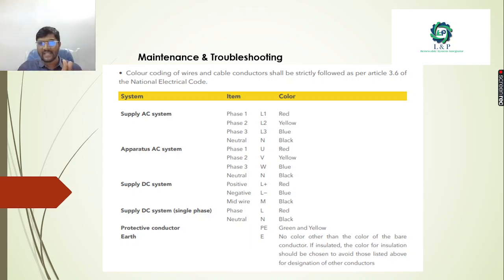For the AC supply side, follow red, yellow, blue, and for a three-phase AC system you need red, yellow, blue and black. For a normal solar DC system, you can use red and black. For the mid wire, you can go with black, and sometimes you can use blue also. For a single phase system, you can use red and black. For protective conductors, always use green and yellow cables. And for earthing, always use copper.